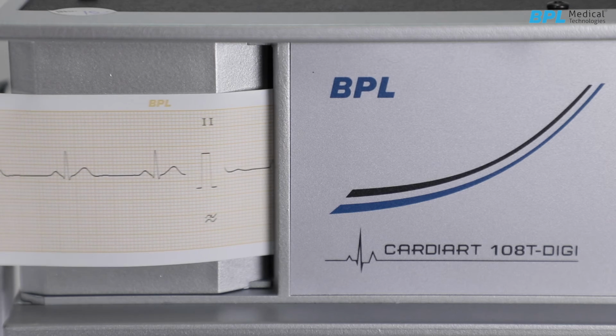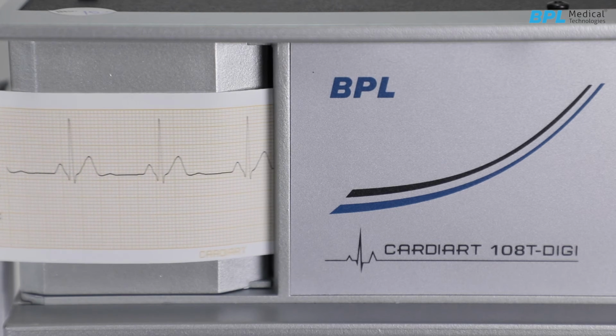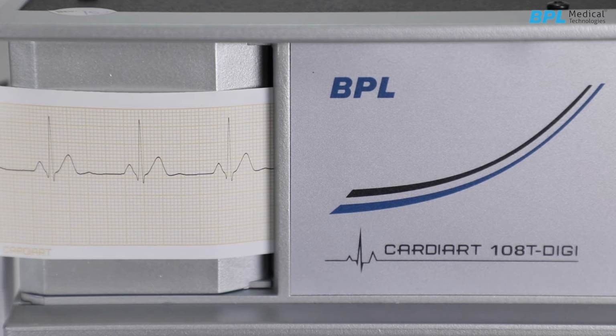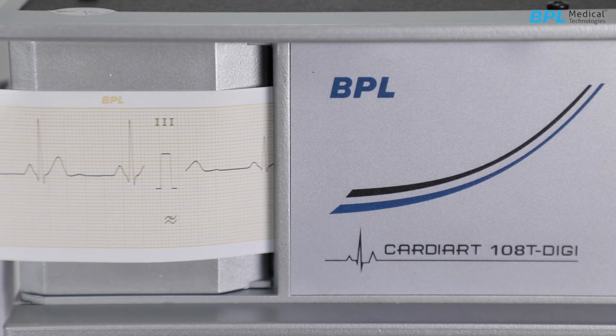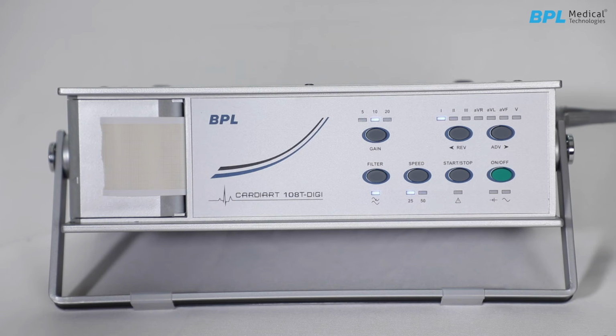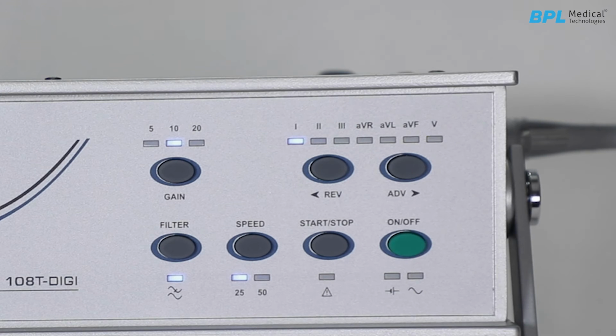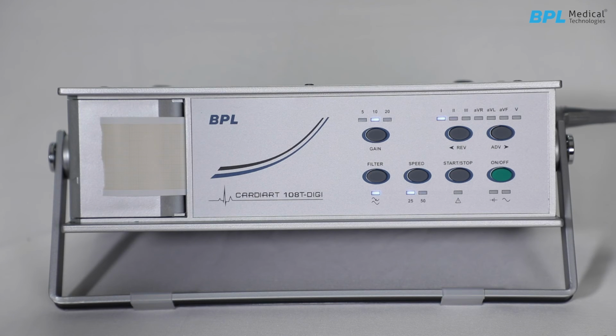While printing the V lead, press the advance key to pause the print job after printing the desired number of QRS complexes for the V lead one. The V lead will start blinking, indicating the printing is paused. This pause can be used to change the position of the chest lead for taking the ECG printing for the other V leads. After placing the electrode in the next V lead position, press the advance key again to print the new V lead. The V lead LED will stop blinking and the lead LED will start blinking for a few seconds before printing. Repeat this step for all the V lead ECG.